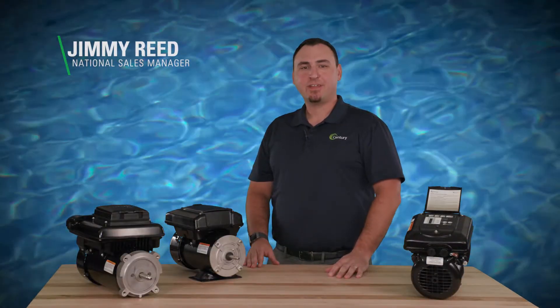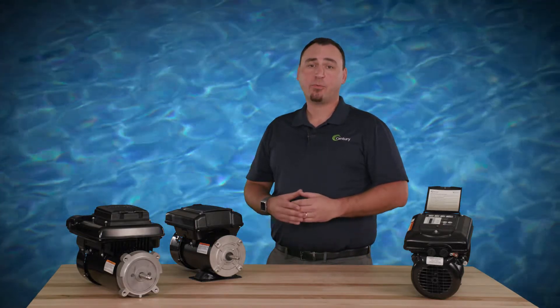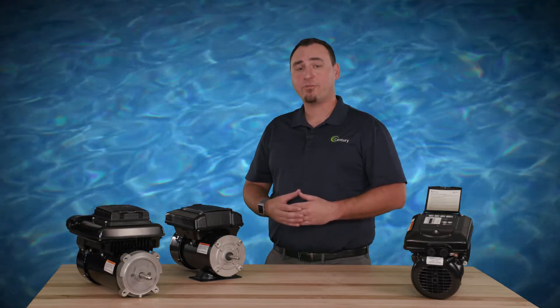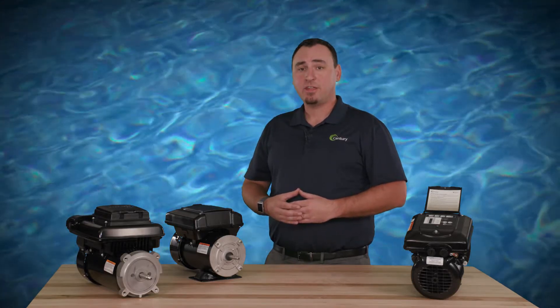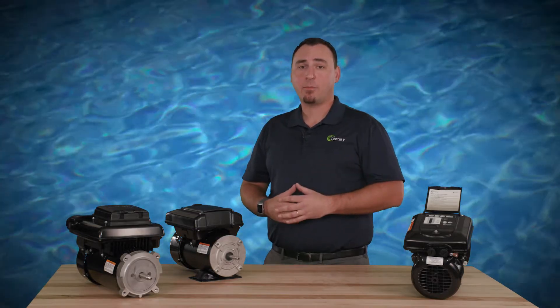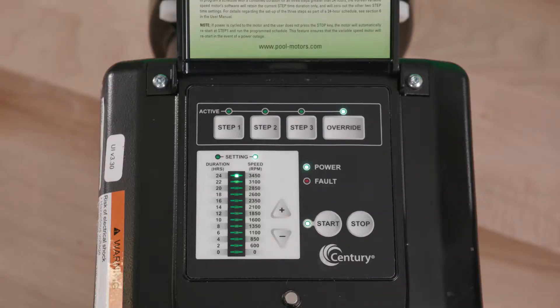Jimmy Reed here with Regal. vgreen motors are equipped with an override feature which can be engaged to temporarily run at higher or lower speeds, ranging between 600 and 3450 RPM. The default setting for this override feature will operate for two hours at 3450 RPM, but can be customized to meet the needs of the pool.